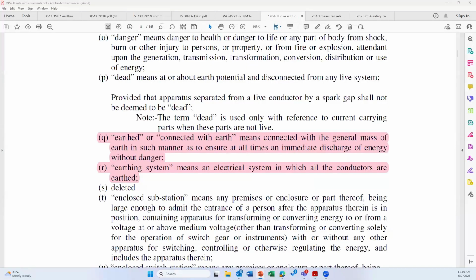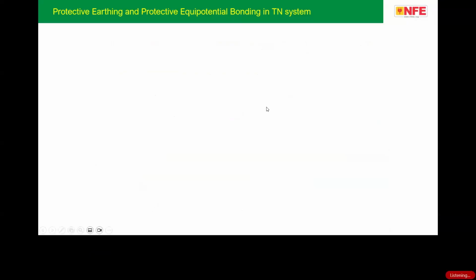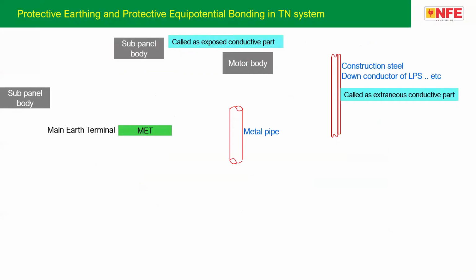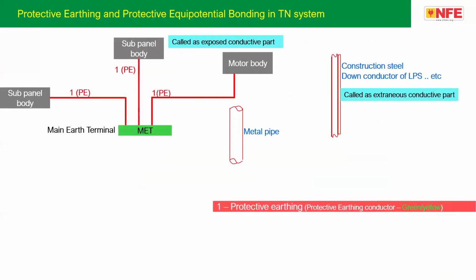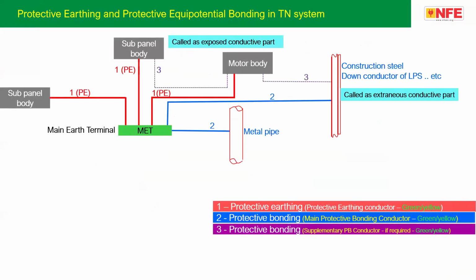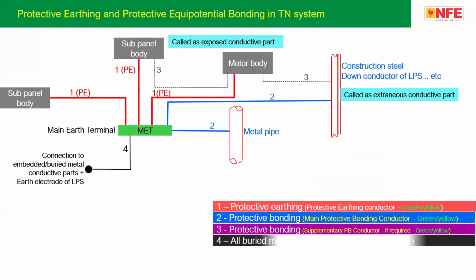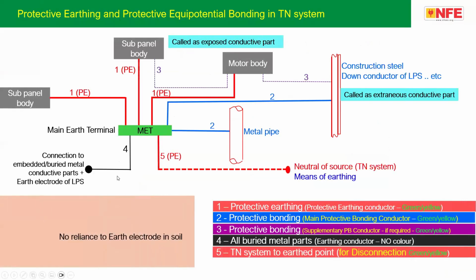However, in the new definition, the meaning of earthing, especially in a building, for example, protective equipotential bonding, as I read in the 2010 and 2020-23 CEA regulation: the exposed conductive parts and extraneous conductive parts are connected to the MET with the help of protective earthing, protective equipotential bonding and supplementary equipotential bonding, and all the buried metal parts are also bonded to the same equipotential bonding bar, which is the earthing conductor. And the MET is connected to the neutral of the source, which is called the means of earthing in a TN system.